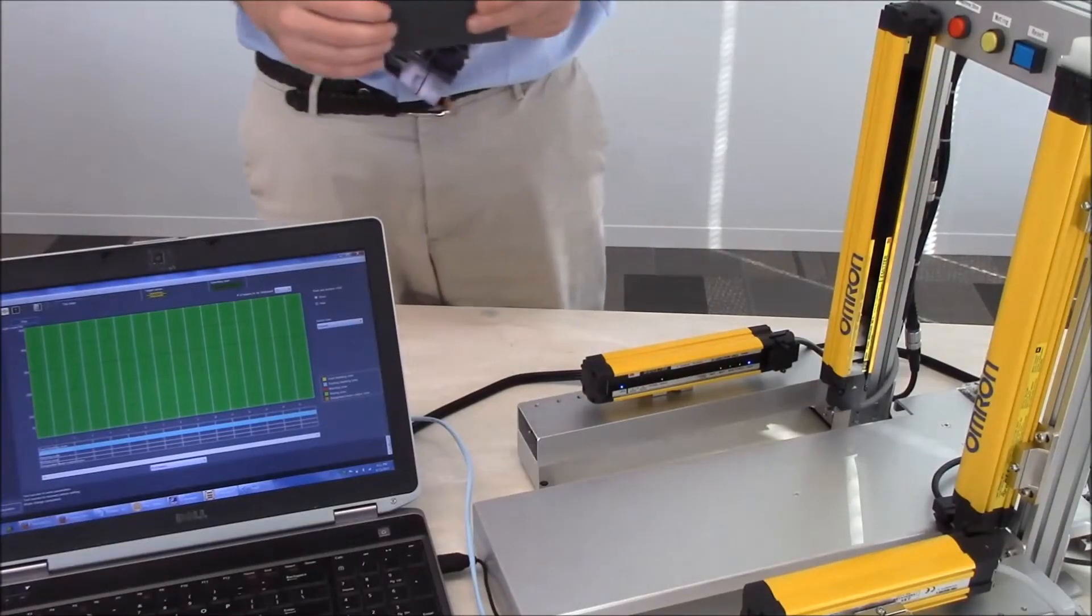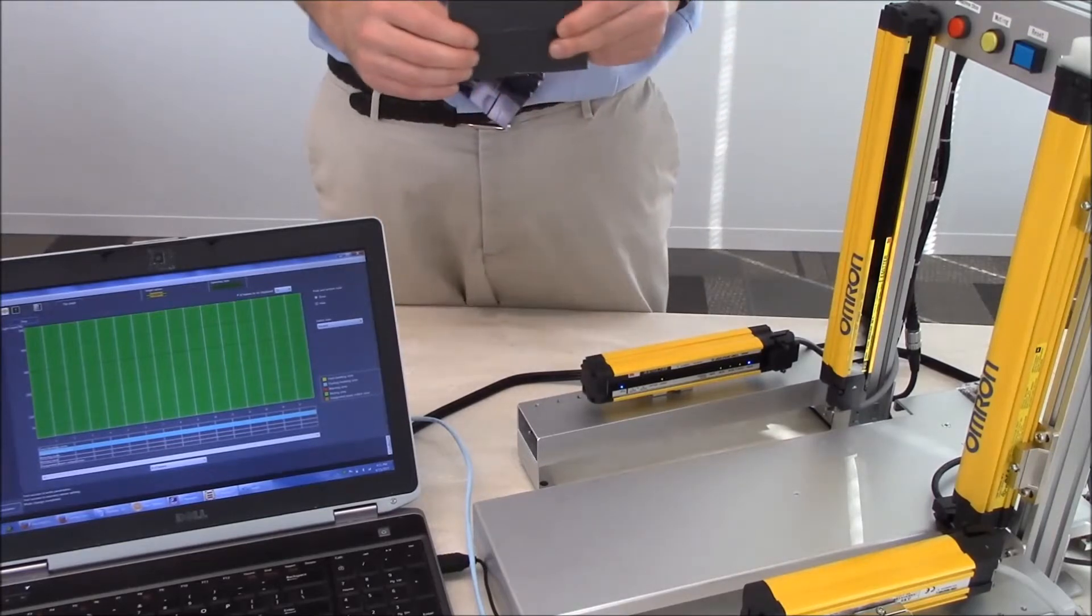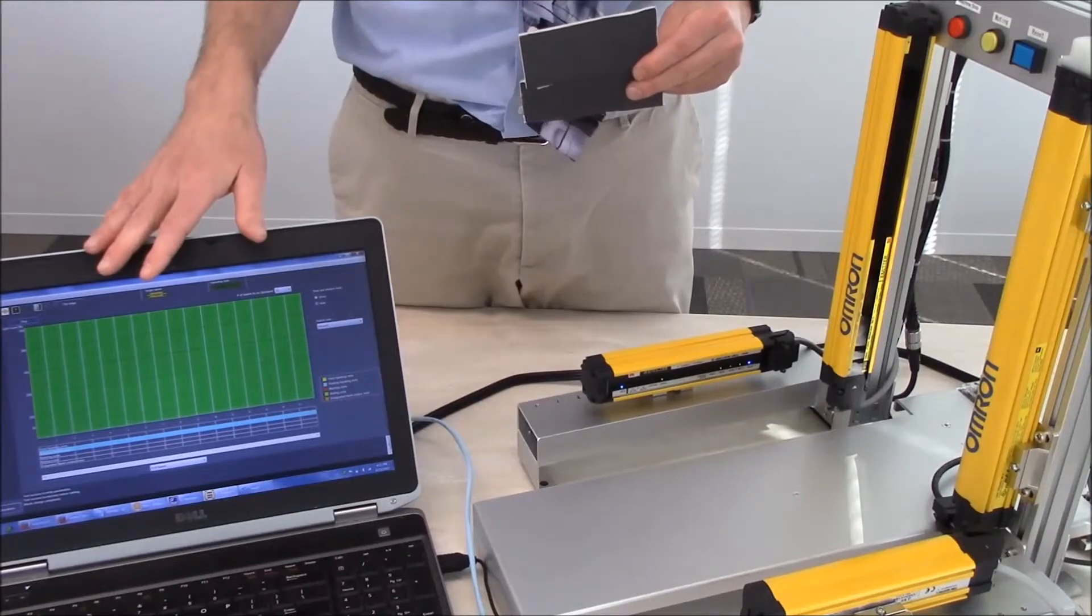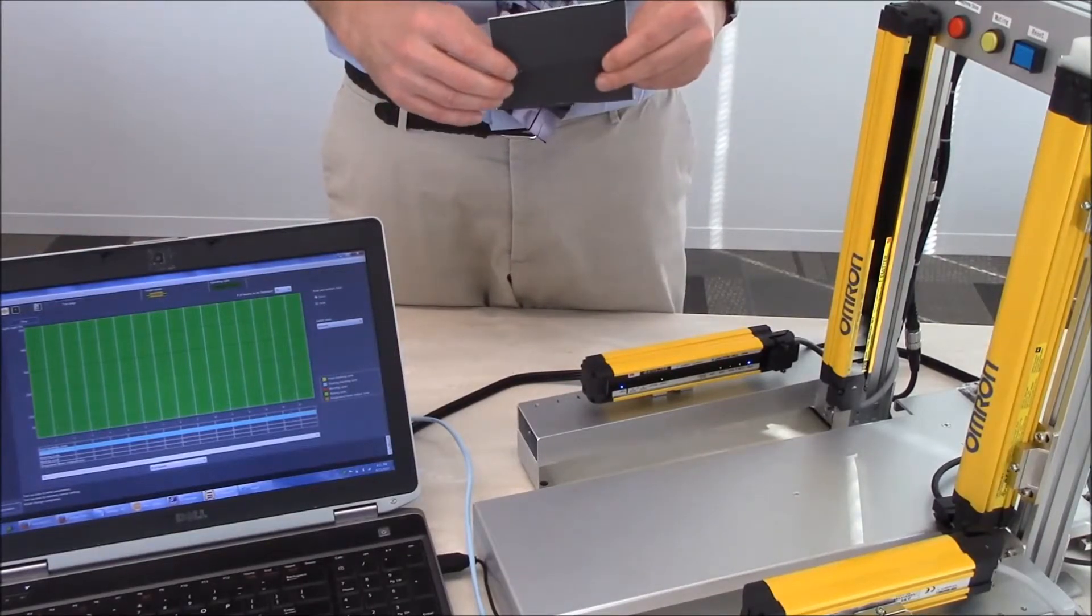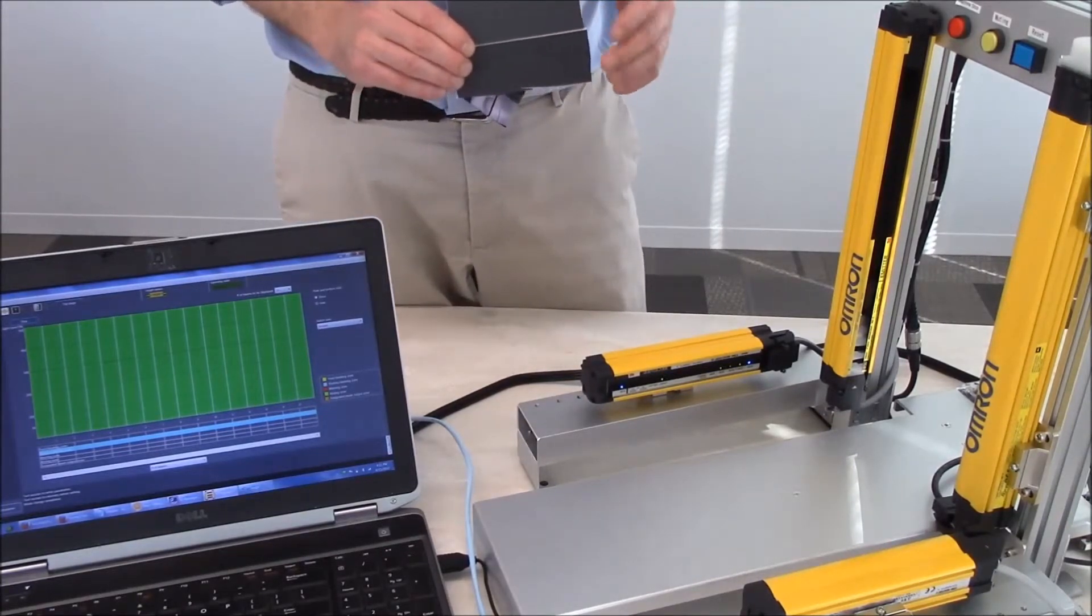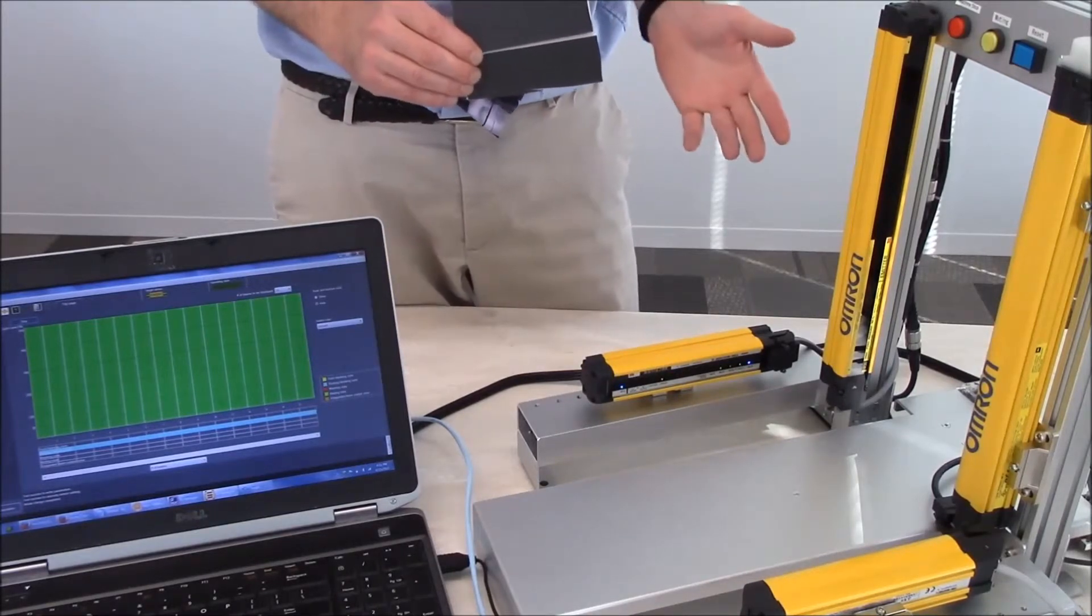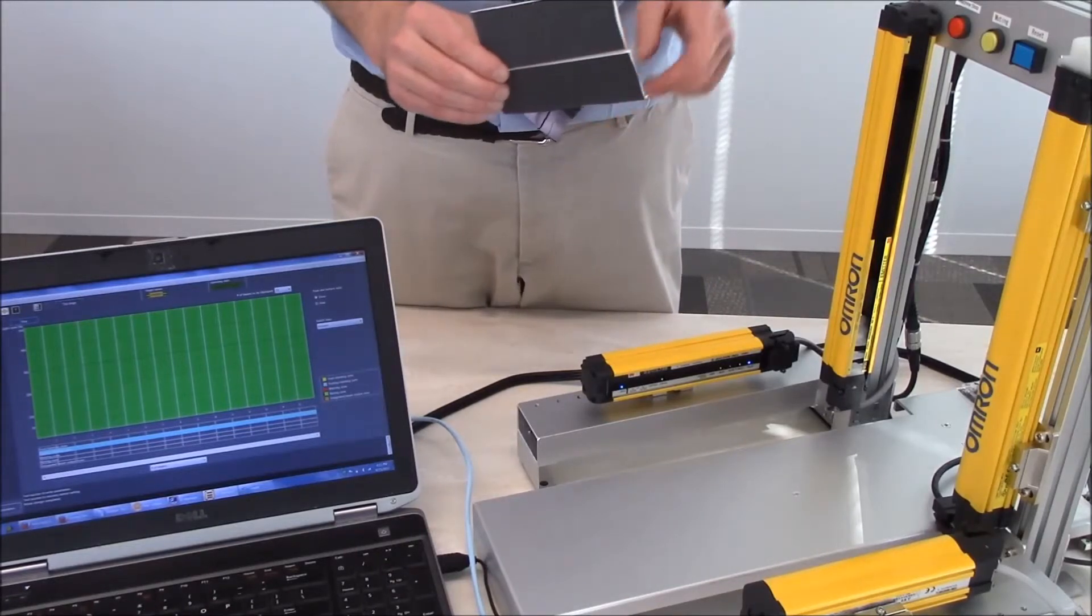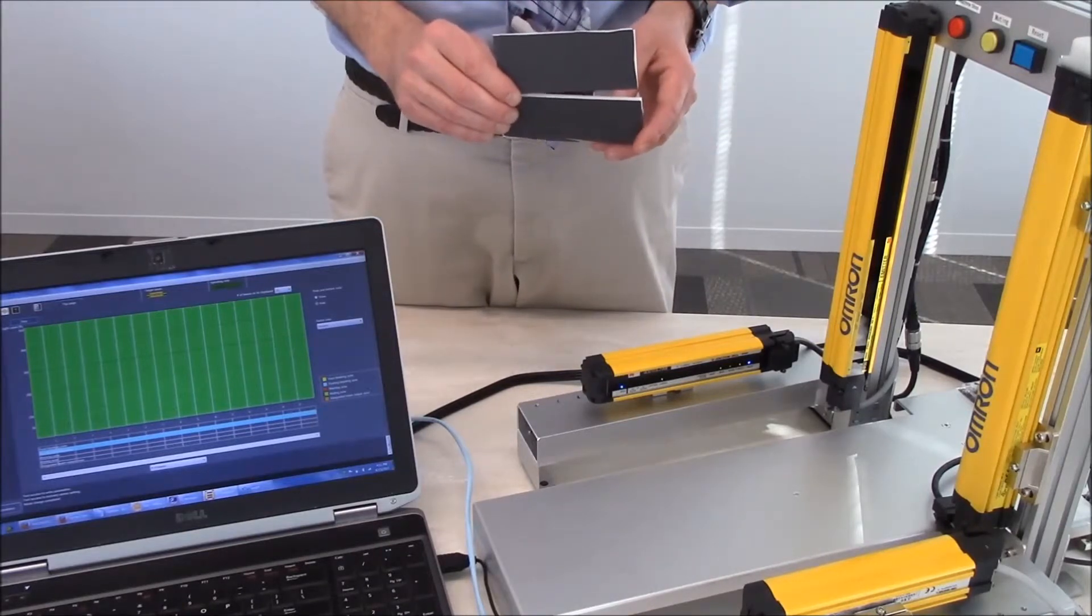Now that we have downloaded the program to the light curtain, presently I am online in the monitor mode with my PC so you can see what is going on within the light curtain itself. Now the thing that is kind of nice about the reduced resolution feature, it is similar to a floating blanking condition but with floating blanking you need to have consecutive beams blocked in order to satisfy the light curtain.